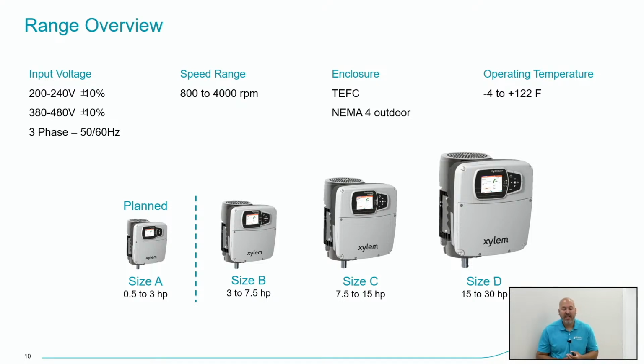So, range overview: there are input voltage ranges from 200 to 240 volt or 380 to 480 volt, with a plus or minus 10% tolerance. These are all three-phase input, dual hertz, 50 or 60 hertz. This is a bit different than what we may be familiar with, but the different voltage ranges are actually due to the motors. There are two different motors, 200 to 240 volt and 380 to 480 volt. The variable frequency drive itself can accept the whole range from 200 volt all the way up to 480 volt. So to give you an idea from a stocking perspective, there are literally only 3 SKUs or part numbers associated with the VFD hardware. It's just a matter of implementing the right programming and software.